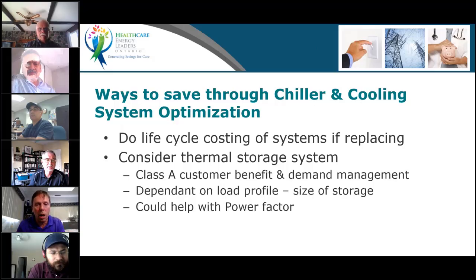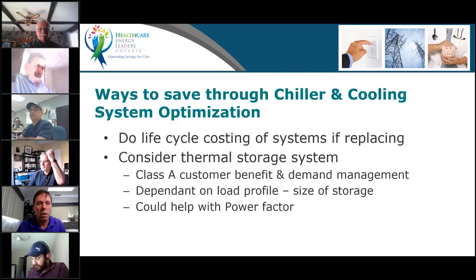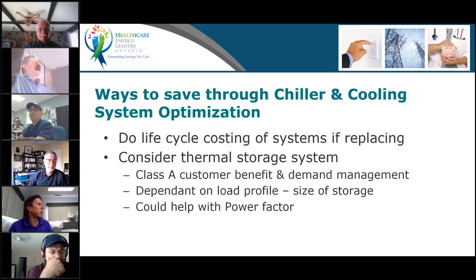Cooling towers that are common to multiple chillers, not if they are dedicated to a chiller each, but cooling towers with VFDs should always be run with parallel operation, as much as their capacity turndown allows, obviously. But that's one thing that we systematically change. We see that less and less, but sometimes people install drives, forget to change the control sequence, and the fans on the cooling tower keep running lead-lag even though they have VFDs. So make sure that is not the case in any of your facilities.